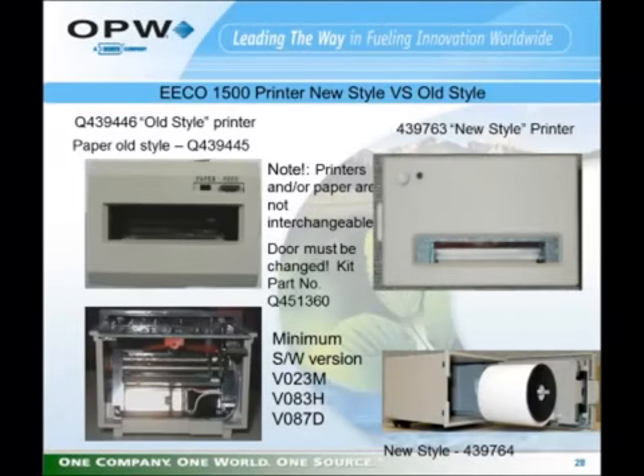The EECO 1500 supports 2 different thermal printers. The original thermal printer is no longer manufactured. That's the printer that's on the left. That printer, Q439446, is designated as the old style printer. It's identified by the fact that the cover comes off of the printer and slides out towards you from the door. That's how you would change the paper in the printer. There is no ribbon because it's a thermal printer. As I said, that printer is no longer manufactured.